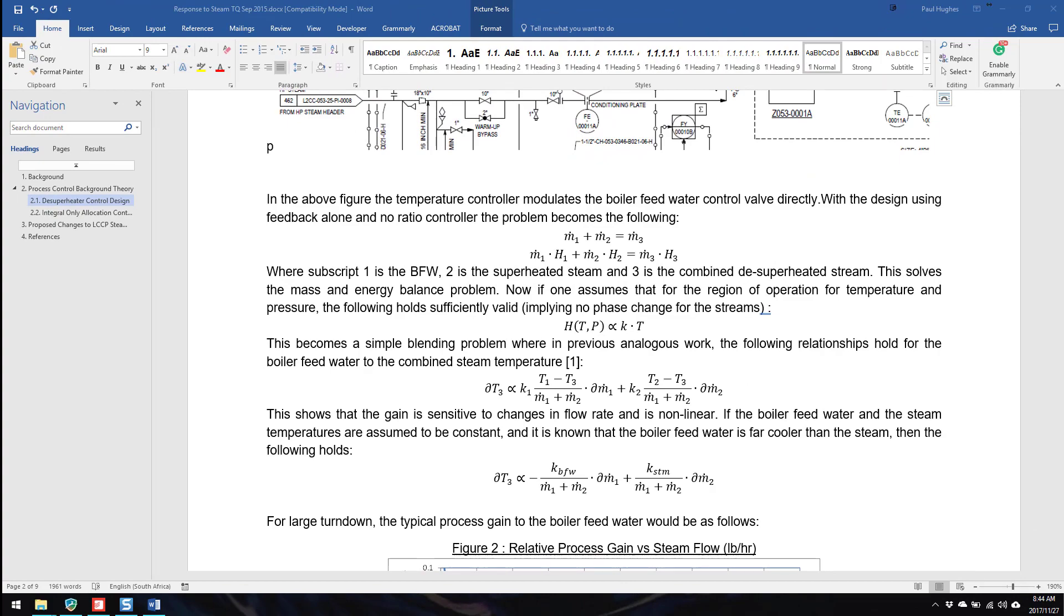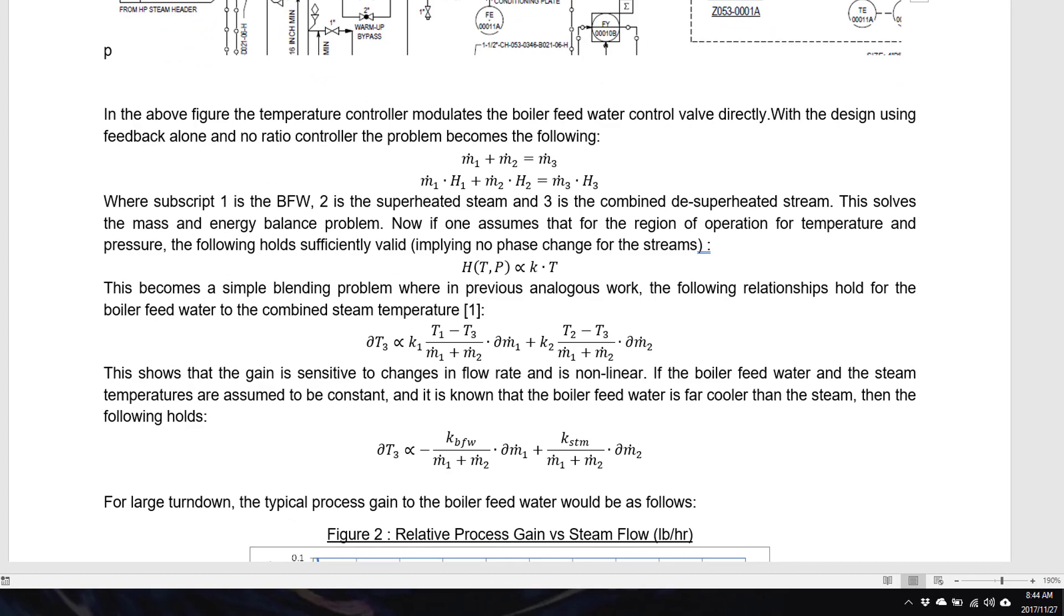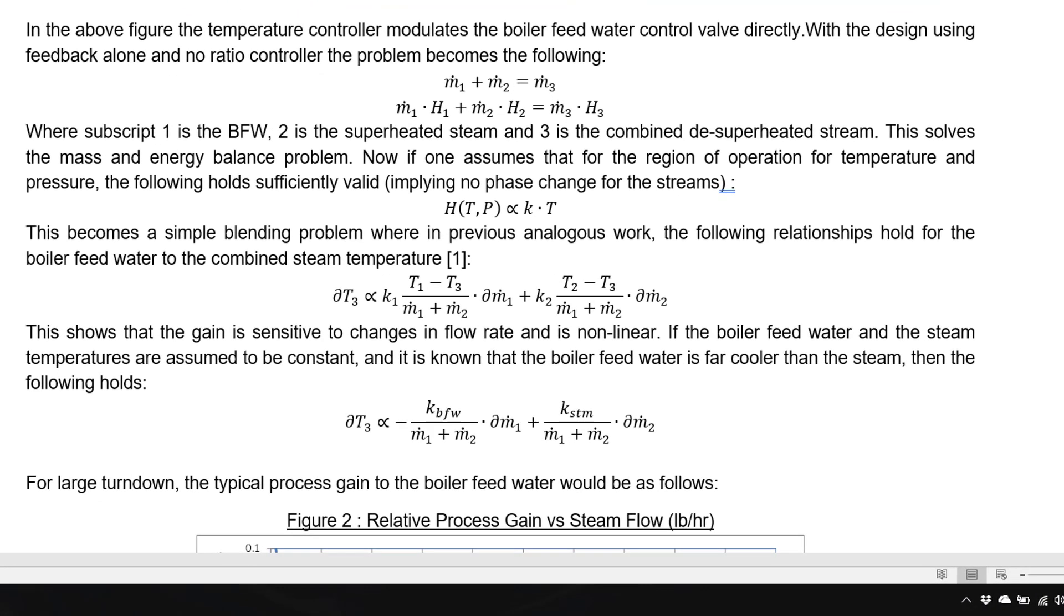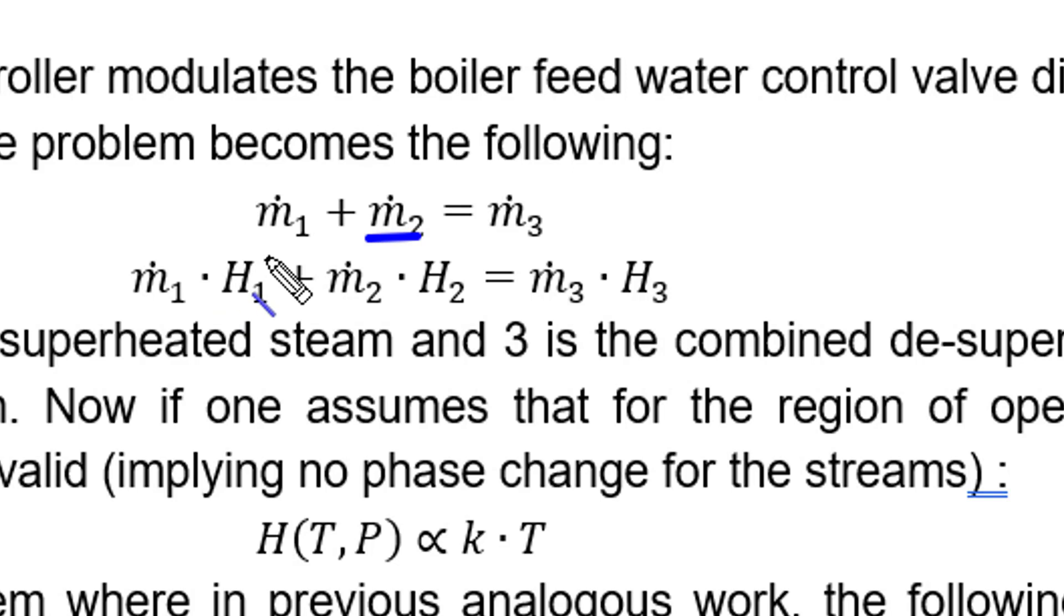Unfortunately I've got to go through a little bit of mathematics to explain the problem. We have a mass balance: m1, the boiler feed water, plus m2, the mass of steam, gives me m3, the combined mass going out. When we do an energy balance, we have m1 times H1 (enthalpy of water) plus m2 times H2 (enthalpy of steam) equals m3 times H3 (combined mass and enthalpy of the final steam quality). We're trying to control H3 because we're trying to control a certain quality—in other words, it's at a certain pressure and temperature.